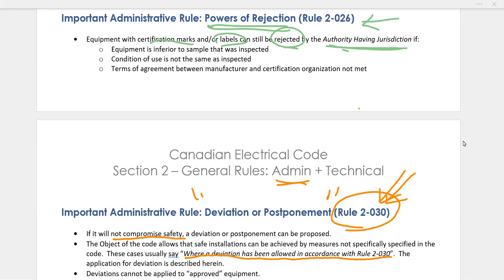When applying for a deviation, the Authority Having Jurisdiction has to review the request and grant the deviation. You must clearly state what you're doing that is different, and you must be granted special permission before the work is commenced — that's an important point. The intent of Rule 2-30 is to allow deviations from code installation requirements; however, it is not intended to seek deviation on approved equipment. Approved equipment is approved specifically, and you do not deviate from that.